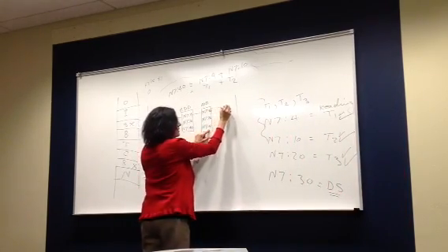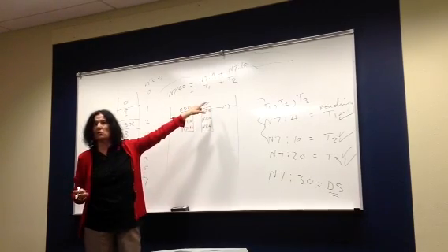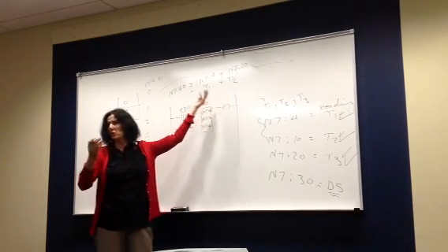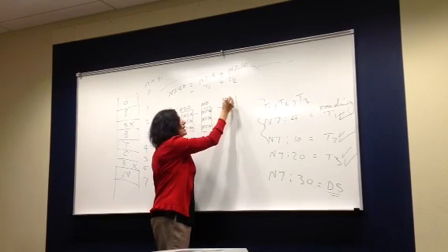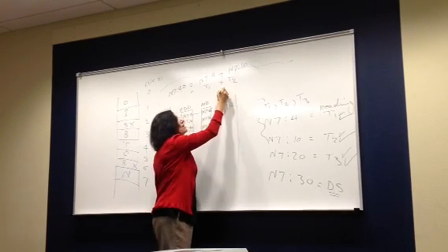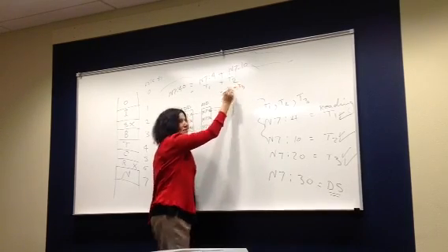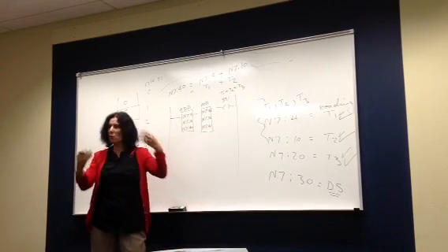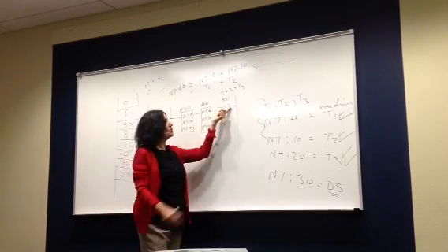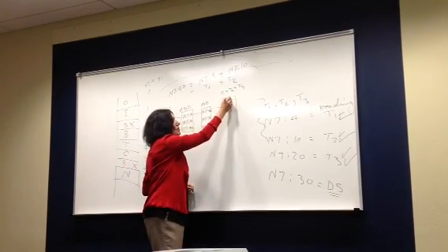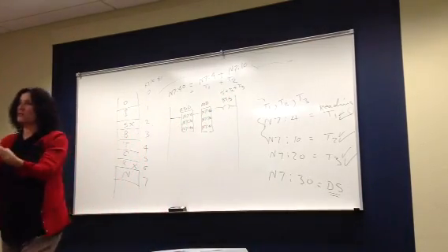Here I really like Siemens because they don't force you to put any out instruction. You can leave it like that. In Allen-Bradley you can use B3/whatever and say transmitter 1 plus transmitter 2 plus transmitter 3. You understand that part? So when this is on, B3/whatever is an indication that we added the 3 transmitters successfully, and nothing happened.